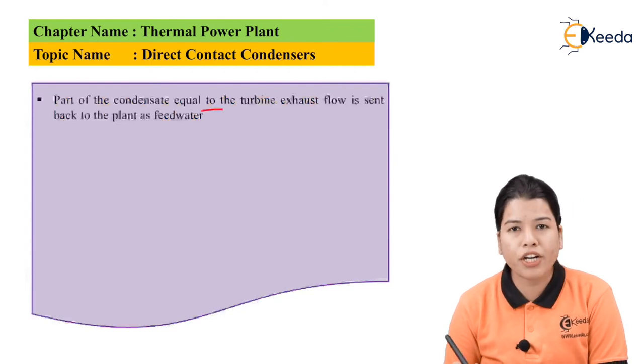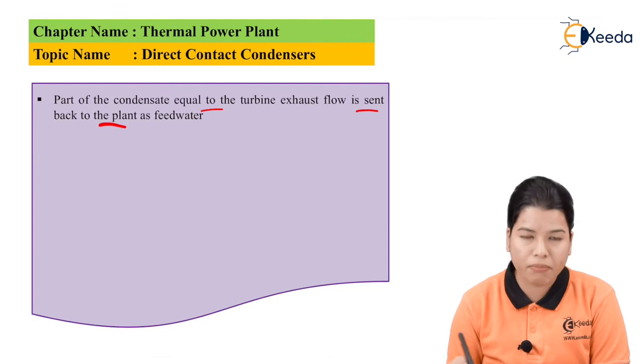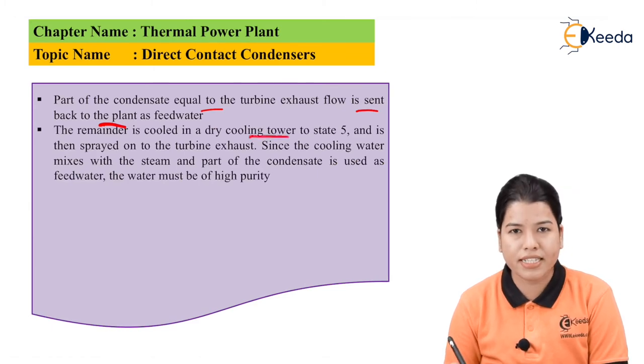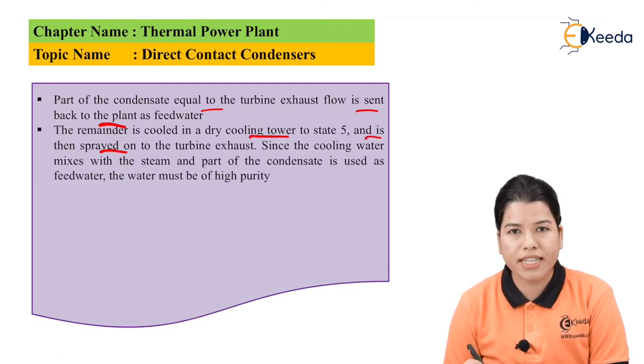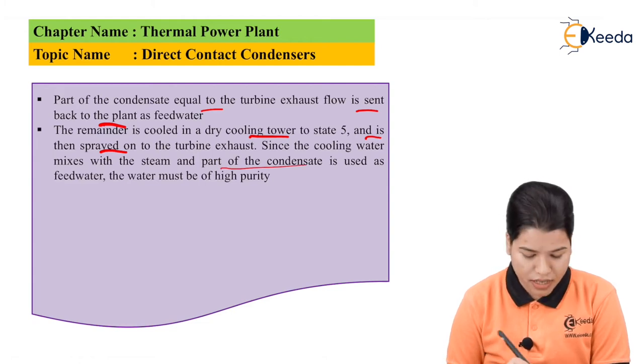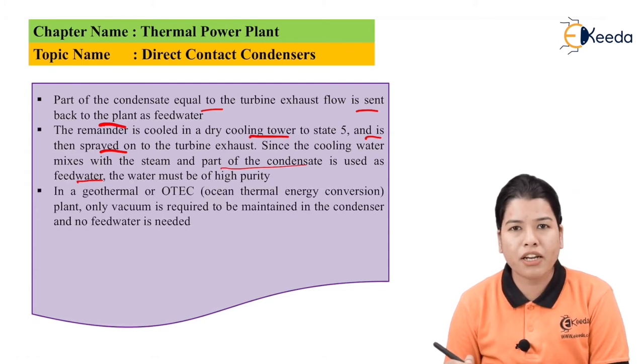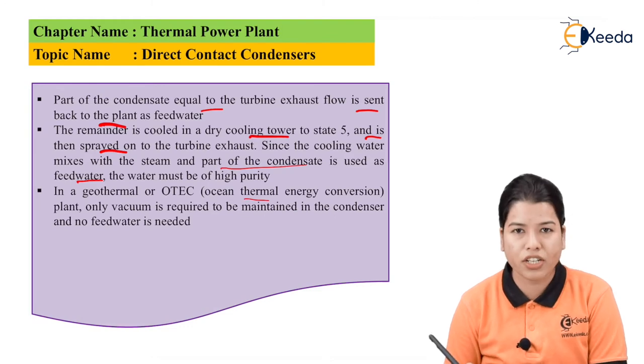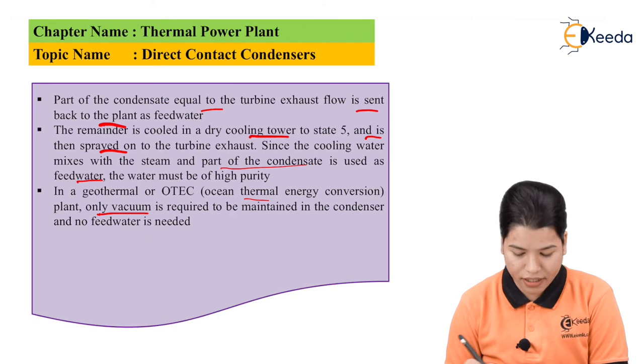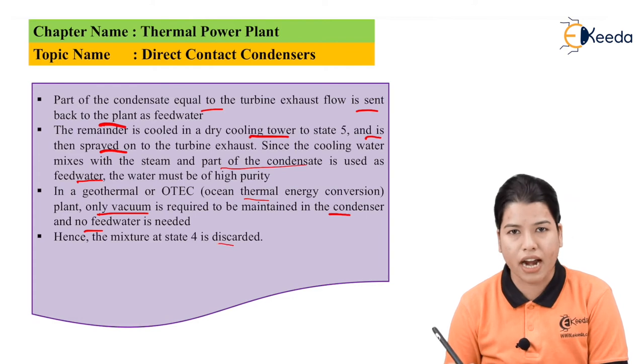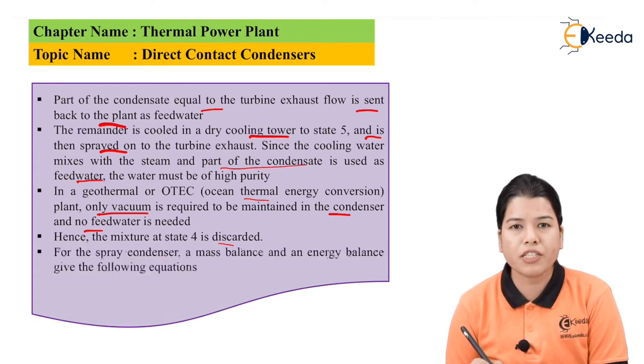Part of the condensate, equal to the turbine exhaust flow, is sent back to the plant as feed water. The remainder is cooled in a dry cooling tower at state 5 and is then sprayed on the turbine exhaust. Since the cooling water mixes with the steam and part of the condensate is used as feed water, the water must be of high quality. In geothermal or OTEC (ocean thermal energy conversion) plants, only a vacuum is required in the condenser and no feed water is needed, but in a thermal power plant, feed water is required, hence the mixture at state 4 can be discarded.